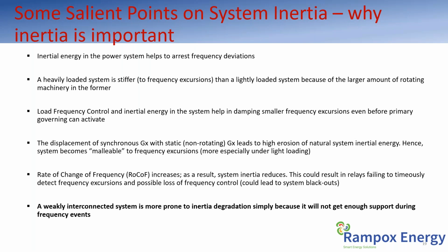This phenomenon is very important because it happens a lot in weak or islanded grids, meaning they don't have support from their neighbors. If there's no support in terms of strong interconnections, the phenomenon of low inertia is even worse, because when you have an event without protection against such extreme cases, you are almost dead. But meshed systems, like your normal Central European systems, are very meshed, so they don't have to study this phenomenon as much, because they always get support from each other very quickly.